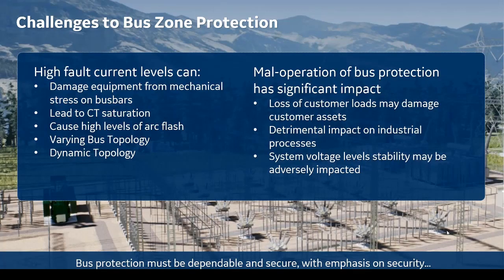Bus topology: how many breakers do you have on the bus? You could have from 4 up to 20-something breakers, depending on the type of bus. So we need to be able to address all of those. And dynamic topologies, meaning reconfiguration of buses. One day generator 1 might be on bus 1, and tomorrow you might switch it over to bus number 2. So you need to be able to deal with those dynamic topologies of buses.